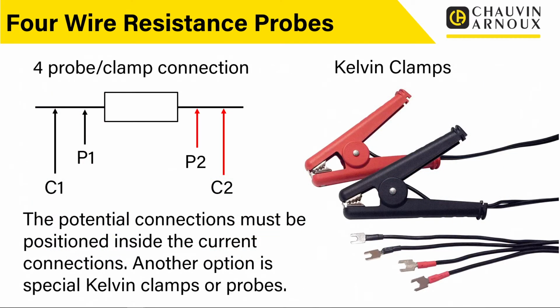So when we're carrying out these measurements, obviously we need to make these connections, and the normal way that we'd make these connections is by using 4 separate clamps or 4 separate probes. You would have 2 current probes, C1 and C2, and 2 potential probes, P1 and P2. Now, when we connect these, we said that we pass the current through the circuit. So that goes through C1 and C2.